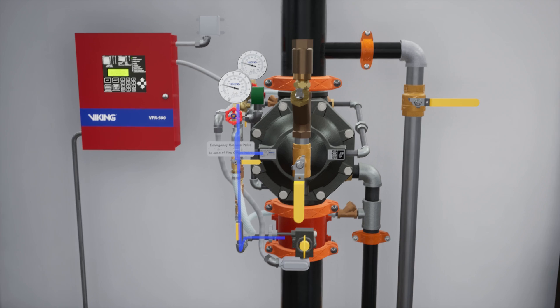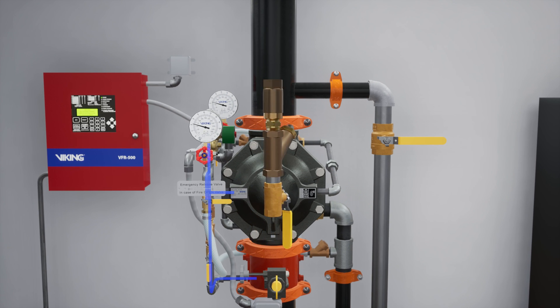The prime line directs water to the prime chamber of the Deluge valve. The prime line consists of an open priming ball valve, a Y strainer, a restricted orifice, and a check valve.